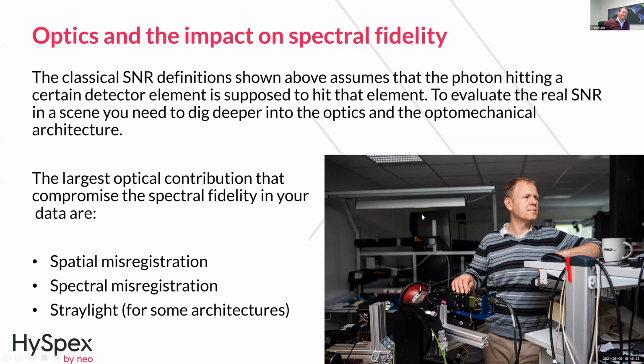The classical signal-to-noise ratio definition shown above assumes that a photon hitting a detector element is supposed to be there. But if you want to evaluate the real signal-to-noise ratio in a scene, you need to dig deeper into the optics and the optomechanical architecture, which I will try to do now. The largest optical contributions that compromise the spectral fidelity in your data are spatial misregistration, spectral misregistration, and stray light for some architectures, not for all.